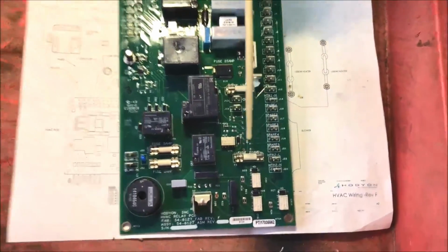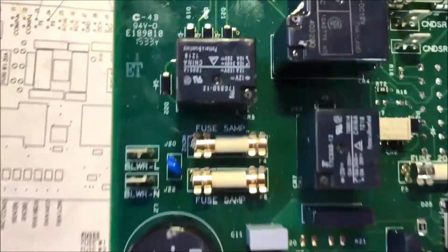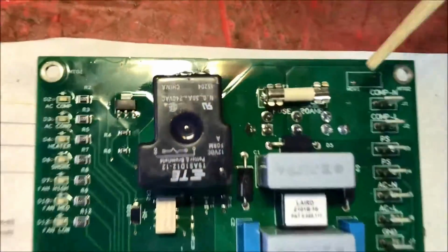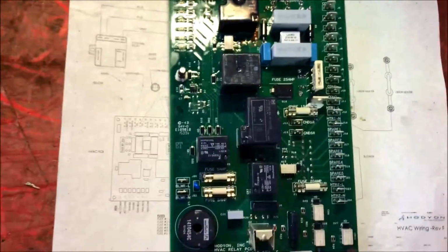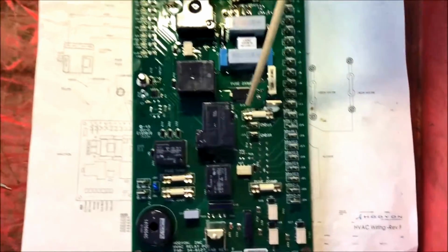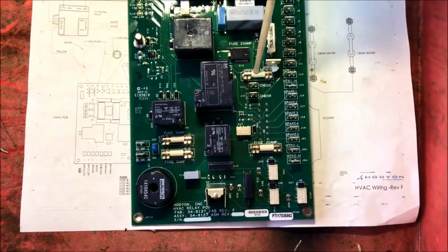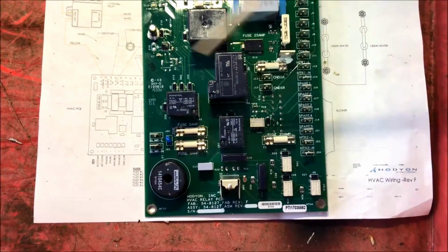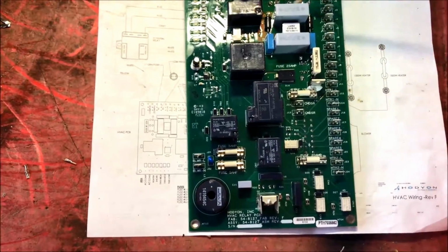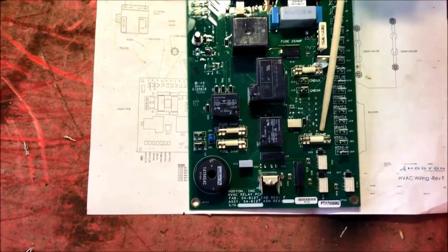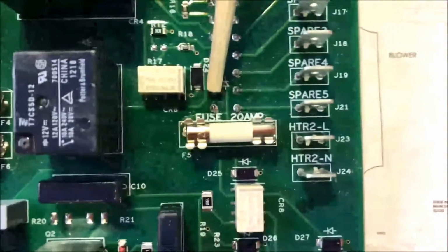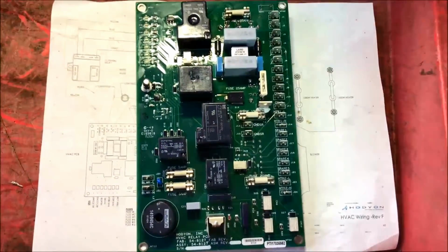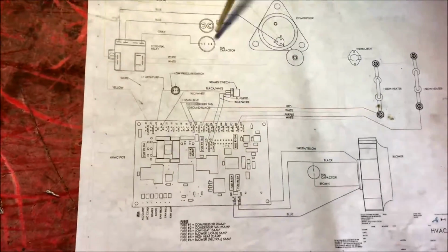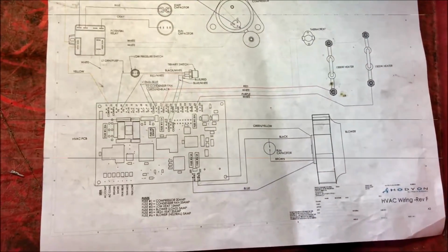These are the fuses for the 120 volt systems. The fuses are ceramic and they're labeled F1, F2, F3, and so on. They also are marked with what their rating is. This one here is a 20 amp, says right there on the circuit board. So the circuit board is labeled very well. If you have any questions, please do call. We also have this wiring diagram available of the whole HVAC system.